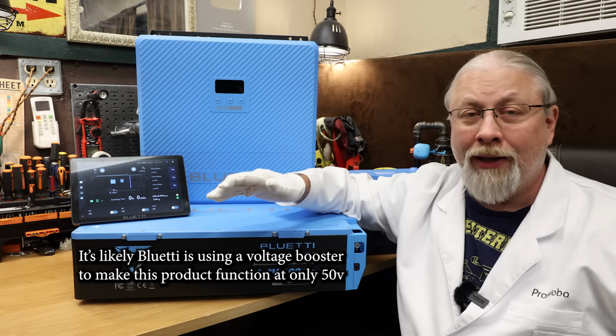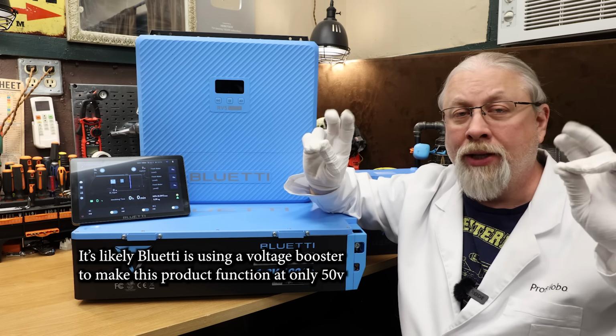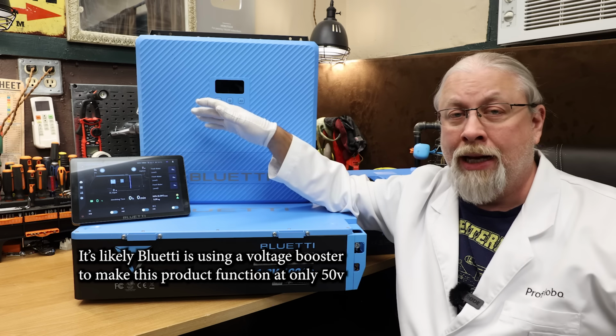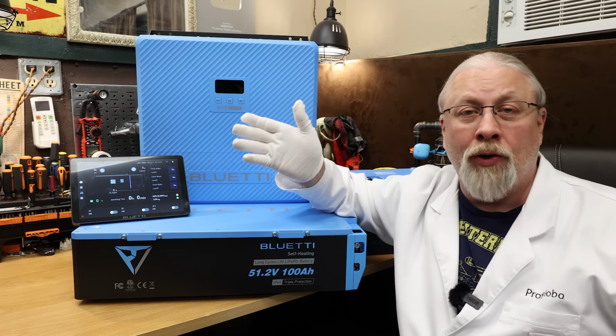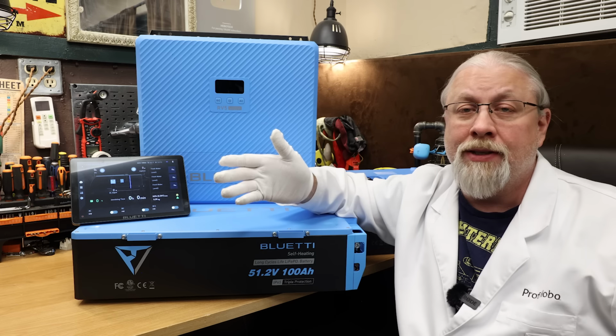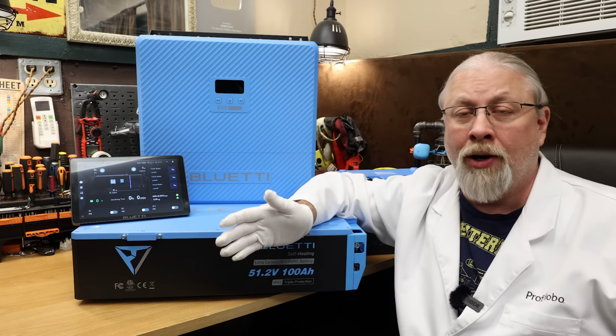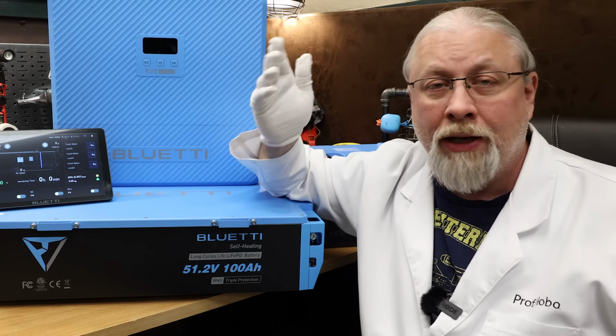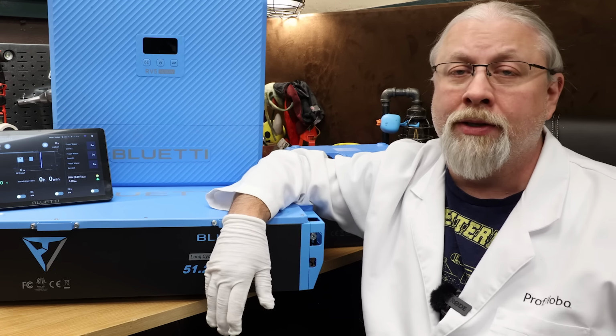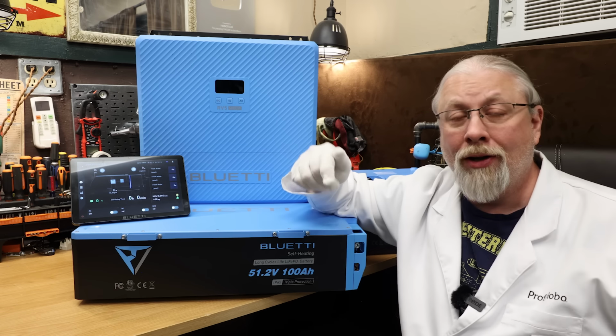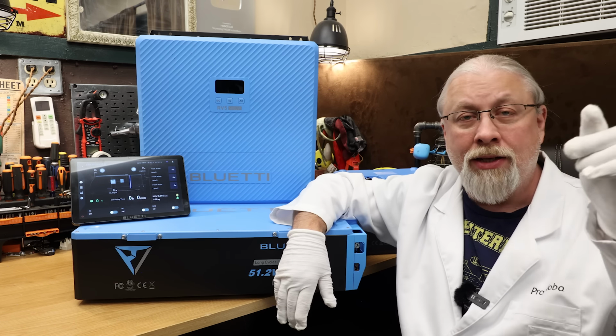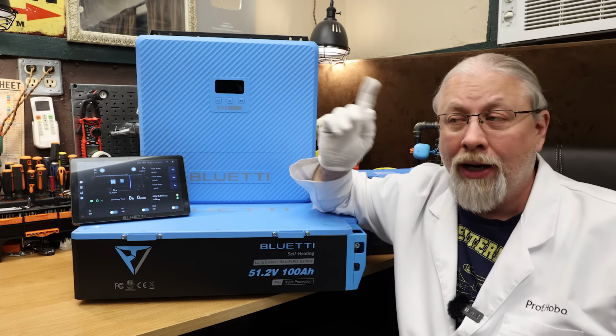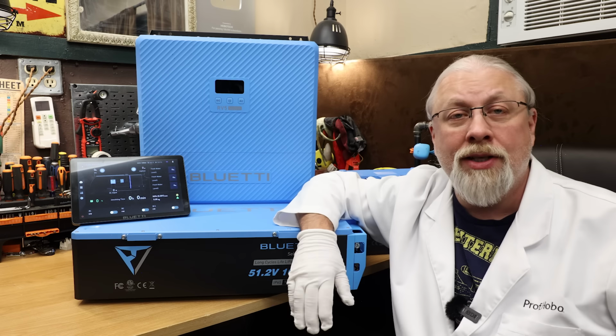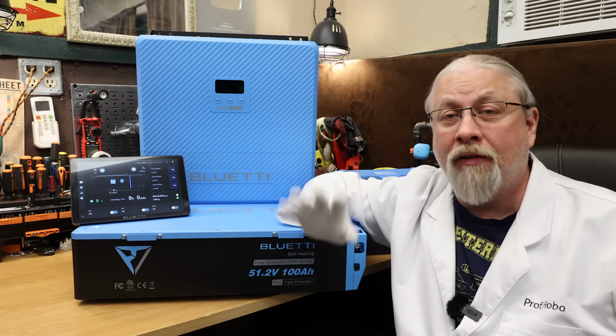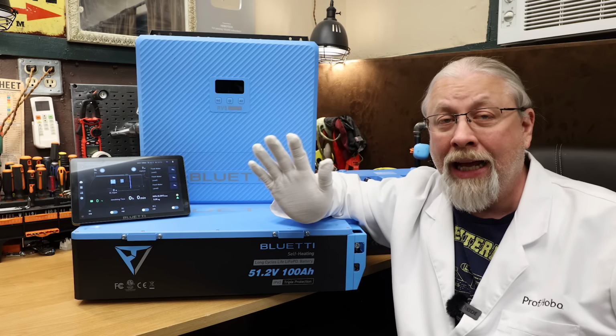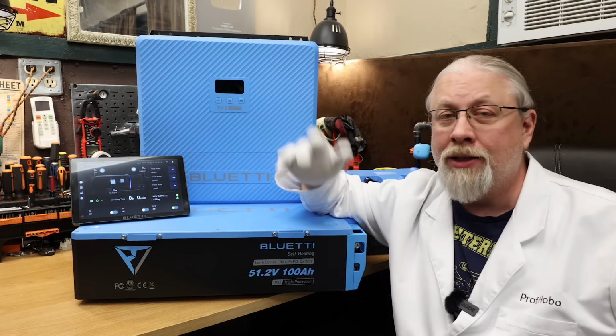There's actually a calculation to figure out the prime voltage range you should aim for with an MPPT controller. If low voltage and high amps was the key to efficiency, then why does every home inverter on the market support 150, 250, 500 or more volts of solar at under 30 amps? My $6,000 home inverter in the next room, running my house with 15,000 watts of MPPT, supports 500 volts of solar at 20 amps, not 50 volts at 200 amps.